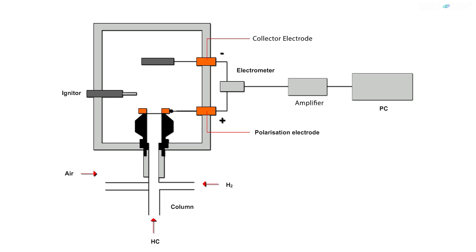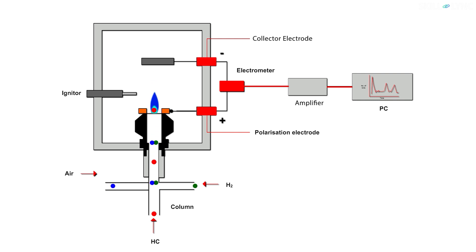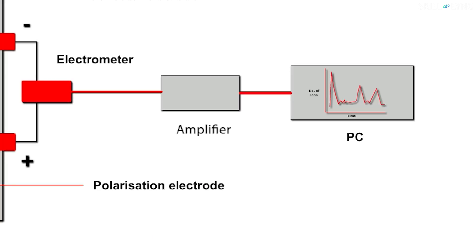Now, let's see how this works. Hydrogen and air are let inside the burner through the respective passages and then the igniter ignites a flame. At this time, the flame will be free from ions. But when a sample gas containing hydrocarbons is introduced through the column, the carbon atoms ionize in the flame and start moving towards the negative electrode. The flow of ions induces an electric current which is measured by the electrometer and amplified in the amplifier. The signal from the amplifier is then fed into the computer which shows the result in the form of an analog display.